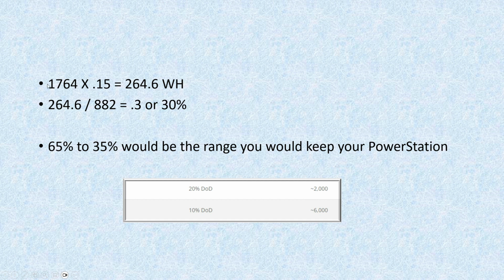Here's the math on it: 1,764 times 15% equals 264.6 watt hours, divided by the 882 watt hours it's rated for, or 30% of the scale. That 882 figure isn't the full scale of the battery's actual capacity—it's a scaled amount, which is why this comes out to 30% of the scale. So if you set your max charge rate at 65% and never let it discharge below 35%, you'd only be using that sliver of power, and you'd get about 4,000 cycles of battery life per Battery University's chart.